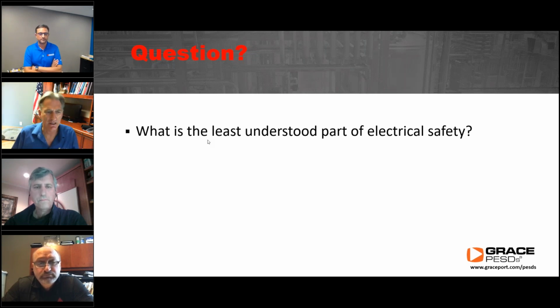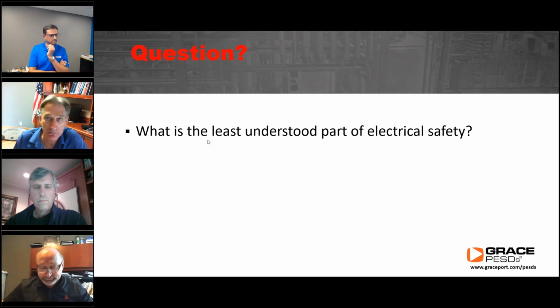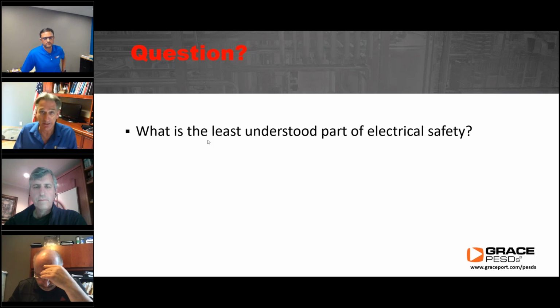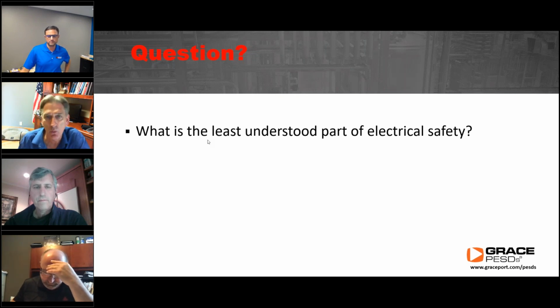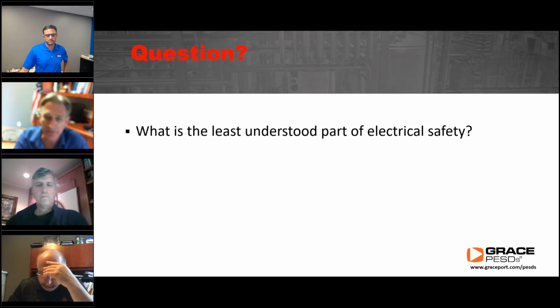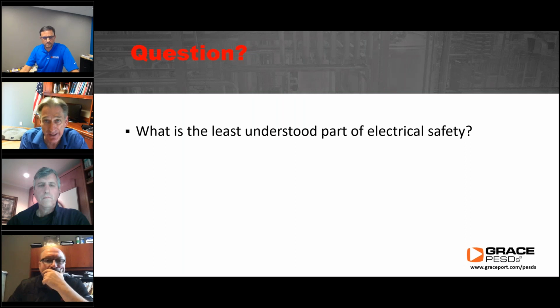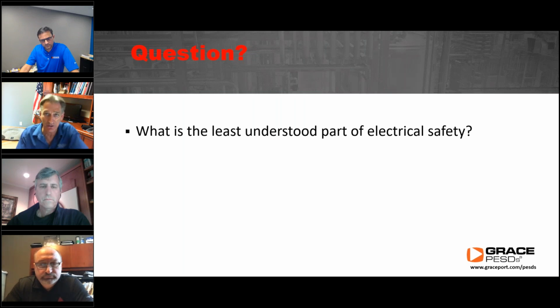One of the things I see when teaching and talking with maintenance workers, electricians, and even safety professionals, I'll go into a plant and someone, maybe the electrical supervisor, says, oh, we don't do any live work. I've heard this more than once. But until we have established and verified that the equipment is in an electrically safe work condition, it is considered live. So we have to be ready, suited up for shock and arc flash, until we have established an electrically safe work condition, until we know the equipment is electrically safe.